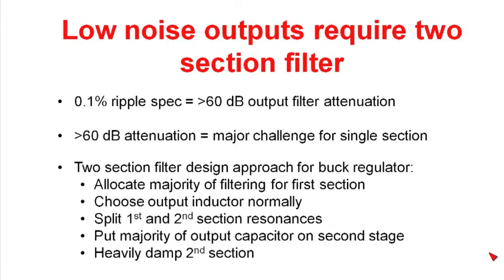There's several major issues in dealing with a two-section filter. One of the big ones is that you have a potential for 360 degrees of phase shift in your filter, and that's going to create quite an issue for your control loop.